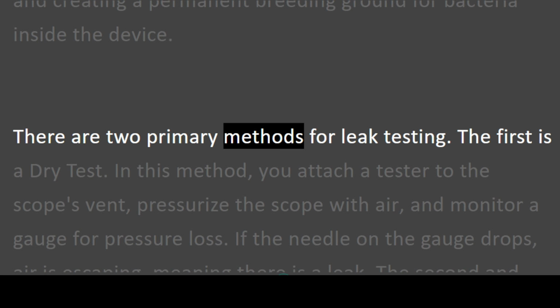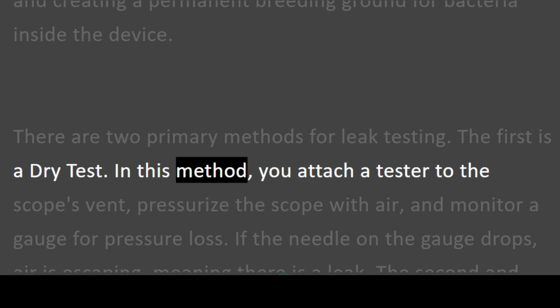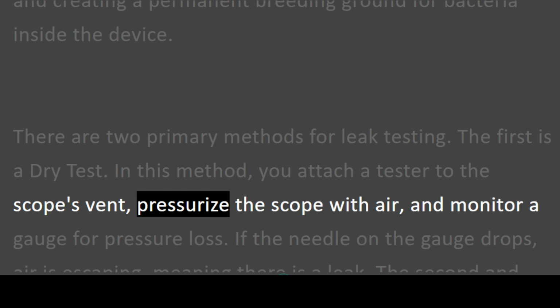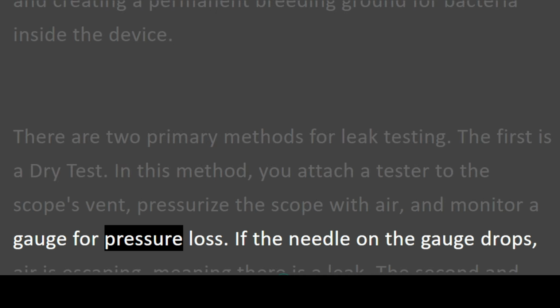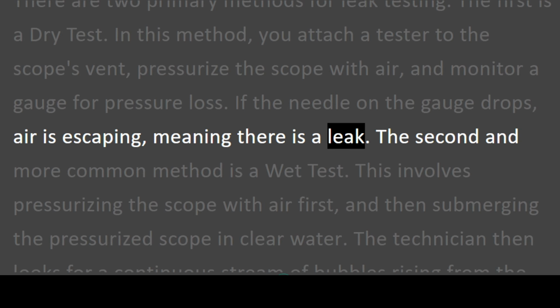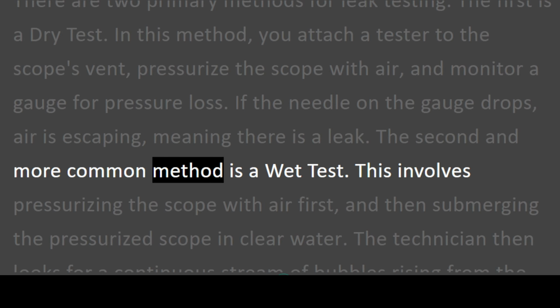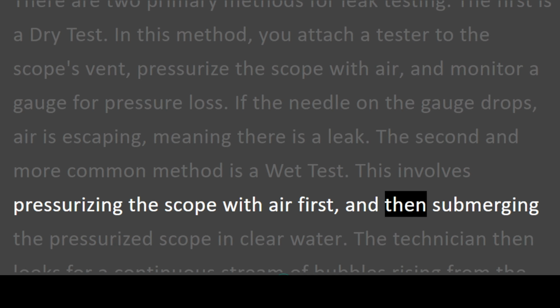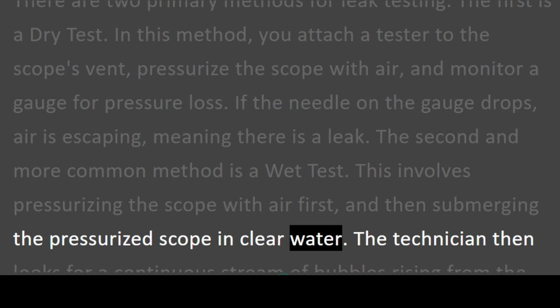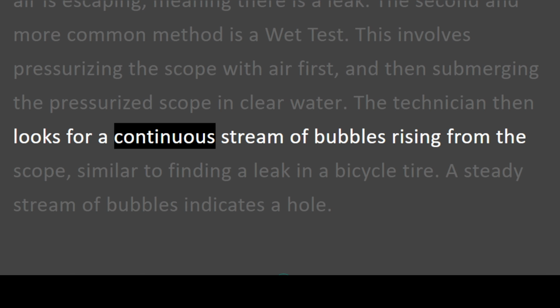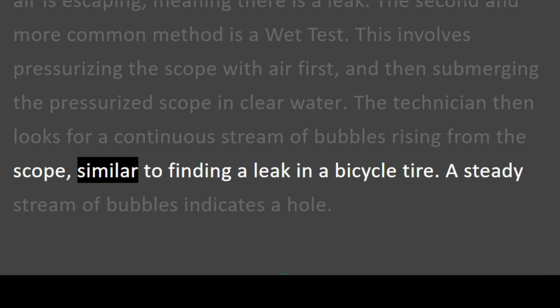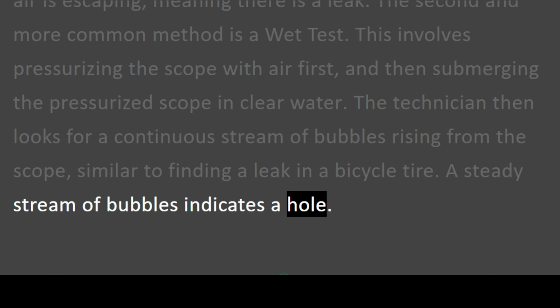There are two primary methods for leak testing. The first is a dry test. In this method, you attach a tester to the scope's vent, pressurize the scope with air, and monitor a gauge for pressure loss. If the needle on the gauge drops, air is escaping, meaning there is a leak. The second and more common method is a wet test. This involves pressurizing the scope with air first, and then submerging the pressurized scope in clear water. The technician then looks for a continuous stream of bubbles rising from the scope, similar to finding a leak in a bicycle tire. A steady stream of bubbles indicates a hole.